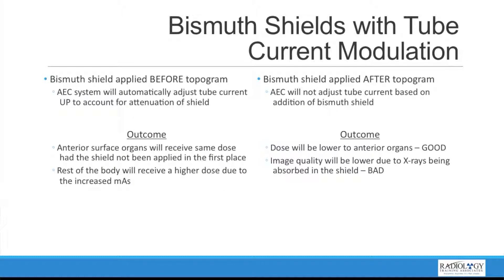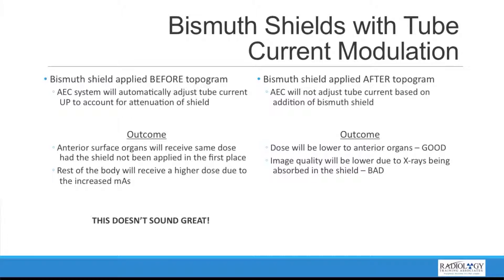If we're using bismuth shields and tube current modulation, there are two ways to apply the shield. If a bismuth shield is applied before the topogram, the automatic exposure control system will adjust the tube current to account for the shield seen in the topogram — meaning the tube current goes up to account for that extra attenuation. The outcome is that the anterior organs receive the same dose as if the shield had never been placed, while the rest of the body receives a higher dose because the mAs has been increased. This doesn't sound like a very good option.